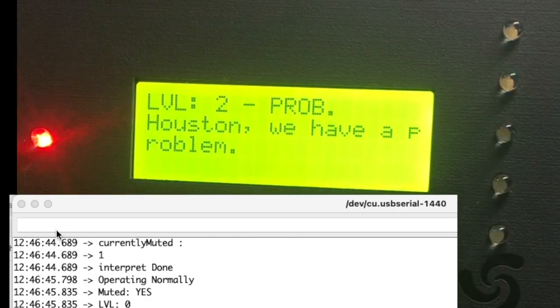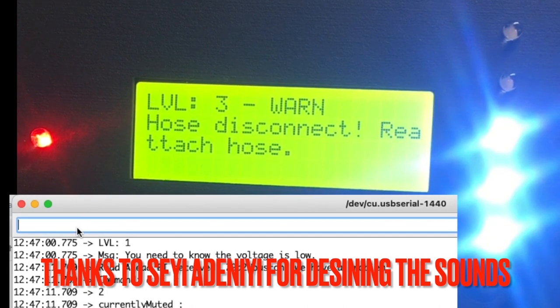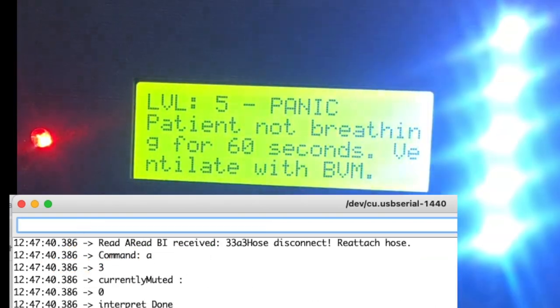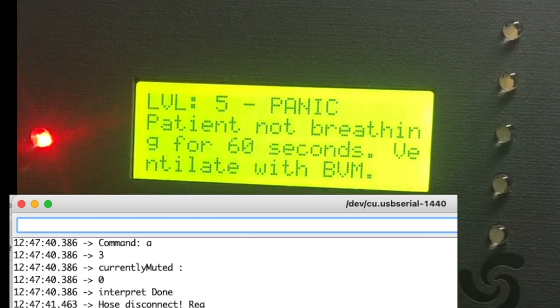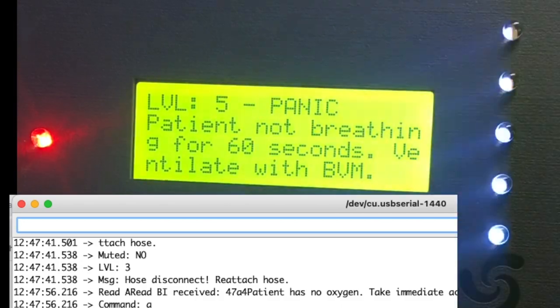Now I'm shifting to alarm level 3 saying a patient's air hose has been disconnected. Now I'm shifting to alarm level 4, saying immediate action should be taken. I can mute the device, although the lights continue to flash while I'm trying to address that problem.